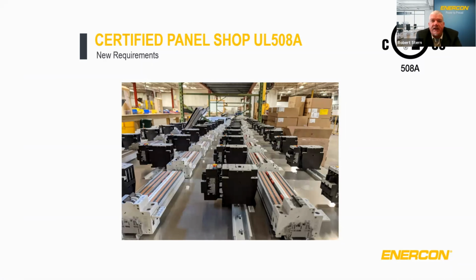So, certified panel shop, UL508A. Some unique things about being a panel shop is that you're going to have to comply with maintaining records, right? Label usage, what kind of product is leaving your shop. We also have to report and request an investigation for configurations that maybe don't comply or aren't prescribed in the current standard. You also have to maintain your tools. So calibration of things like your screwdrivers for terminals, you've got to make sure that for that gauge and size bolt that you're tightening them specifically, and that your tools have a calibration schedule that you're maintaining. You're also going to work with the UL field representatives when required. So if you've got some product out there in the market and something's wrong or needs to be updated, you need to be able to work with the UL field representative to make sure that gets handled. And of course, you've got to provide a qualified factory representative. Next page.